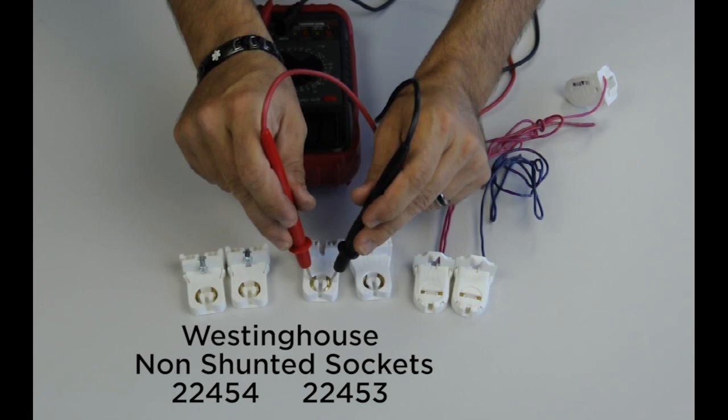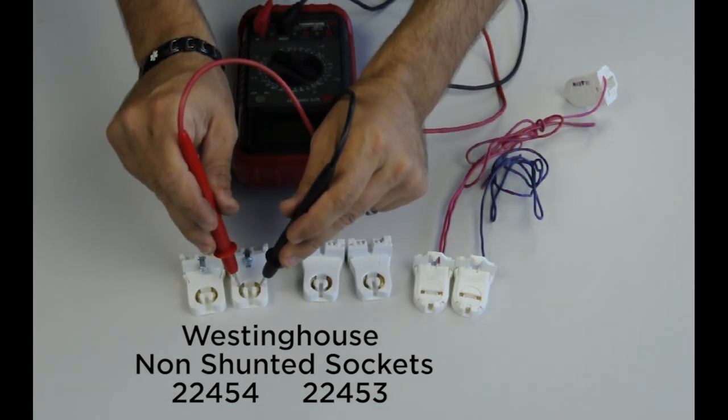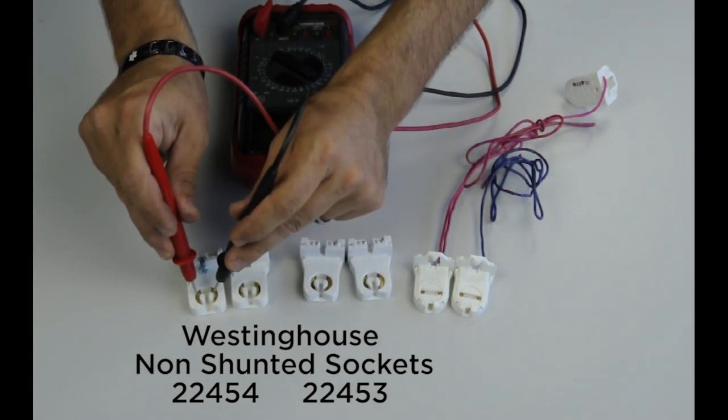For TLED ballast bypass lamps, we need non-shunted sockets with no continuity.